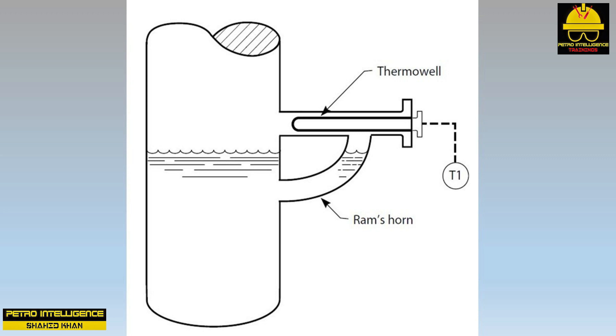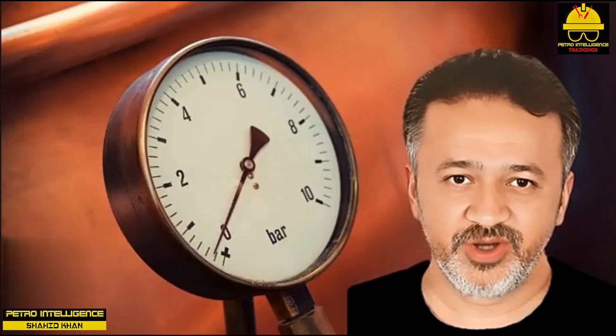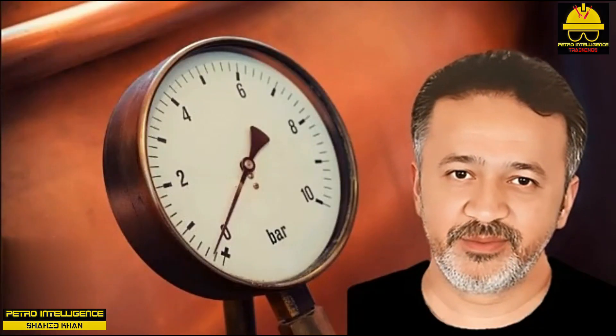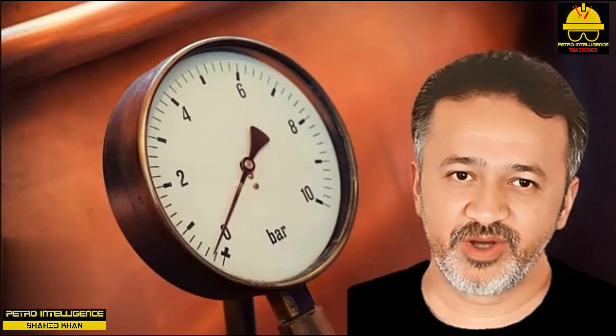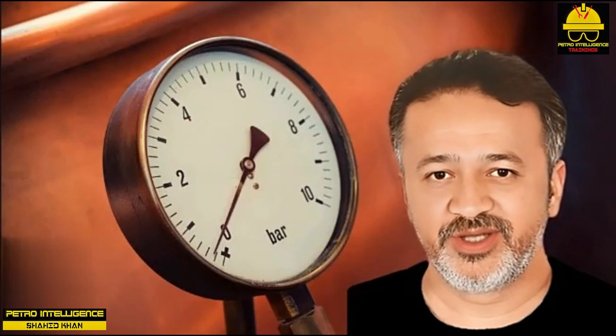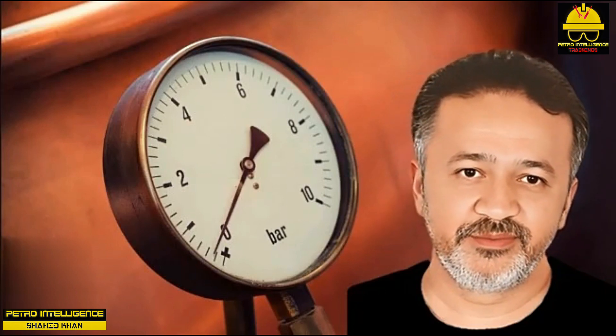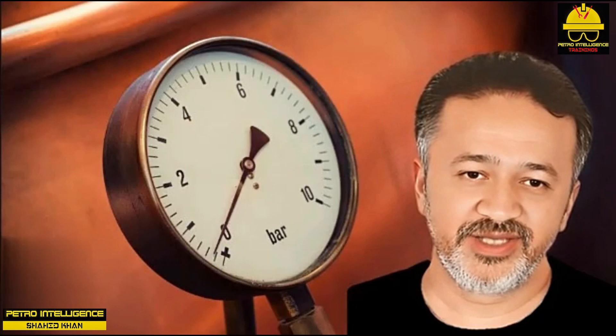If two temperature readings from the same process point disagree, the temperature indication is more likely to be accurate than the temperature control signal. The temperature signal used for control has usually been converted from its direct millivolt output to operate a control station, whereas the temperature indication is generated directly from the thermocouple junction — giving less chance for error. Thank you for watching — please follow the Petro Intelligence YouTube channel for more videos.